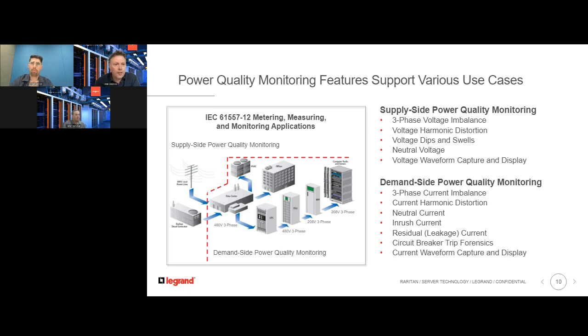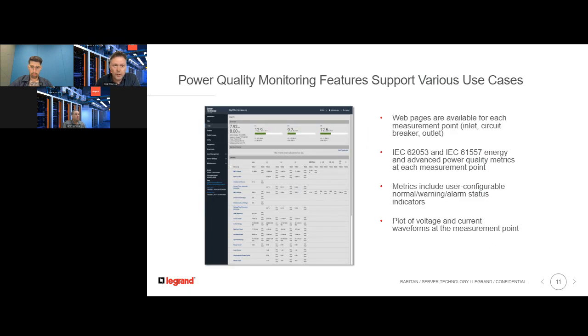So now features like three-phase current imbalance, current harmonic distortion, neutral current, inrush current measurement, residual or leakage current measurement, circuit breaker trip forensics, this is what Calvin talked about earlier, and also current waveform capture and display are available on the new generation PDUs. So all this measurement data is available on the web user interface of the PDU. You can see power quality related information for all inlets and also for every individual outlet. Also the branches behind circuit breakers are getting measured individually.